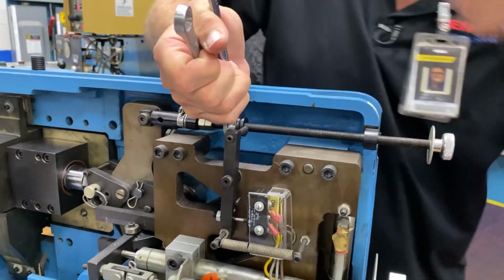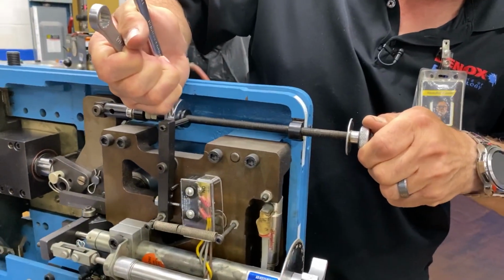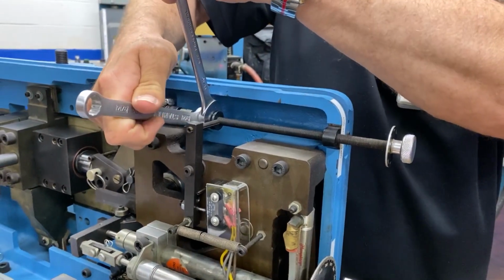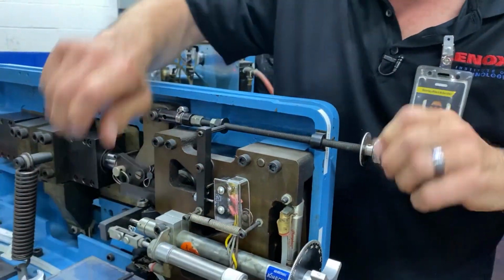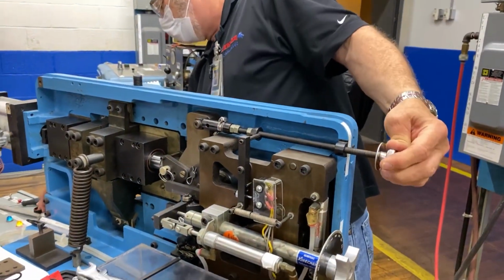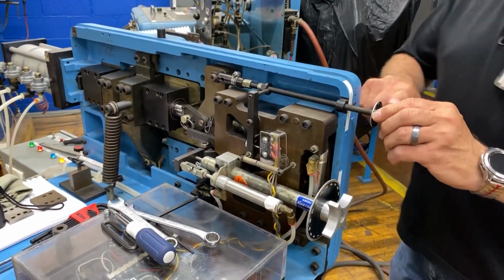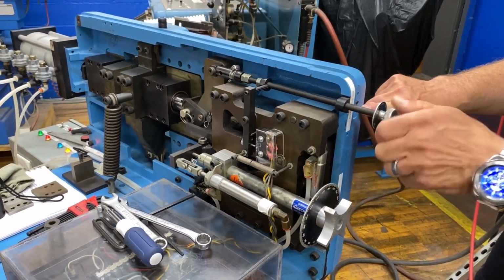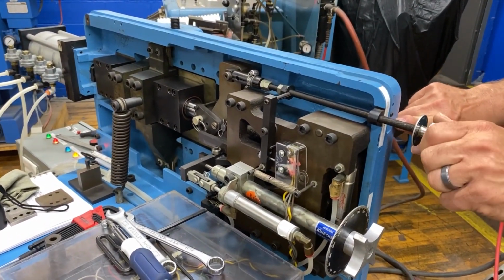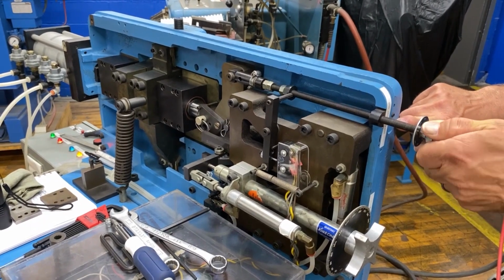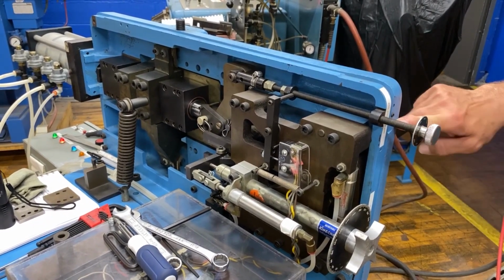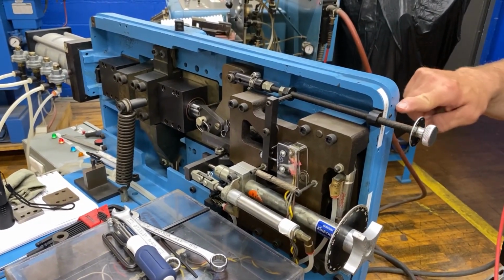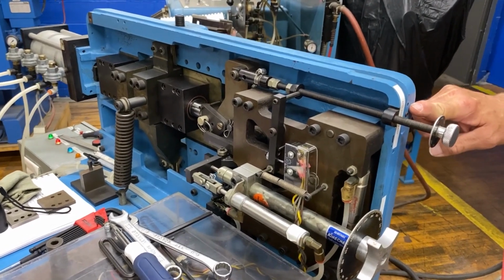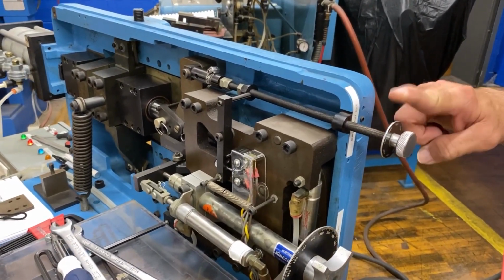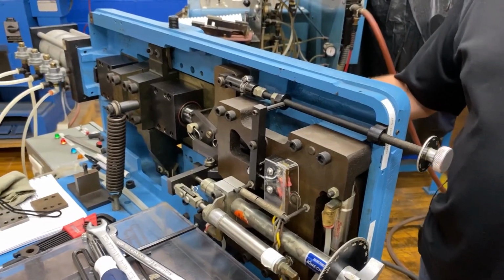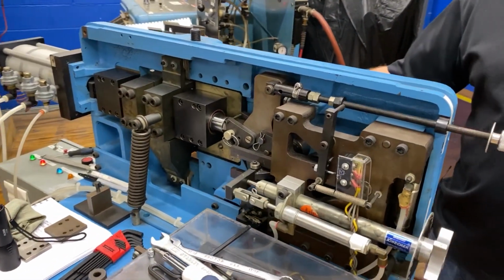Loosen that, and now I'm going to make my adjustment and re-snug the position, then repeat the process. Bring that back in, make sure my light's on. Come back over, there's my 1 turn, coming around, watching my light. It goes off, and there's my 0, so that's my 2 turns. So my current cutout has been calibrated to the 165 thousandths neutral point.